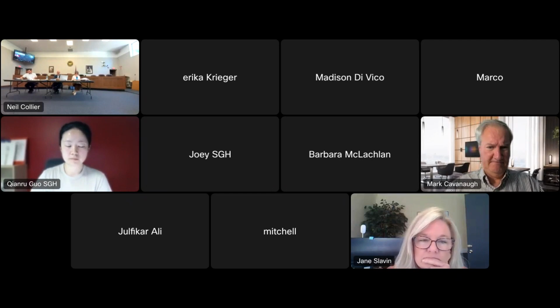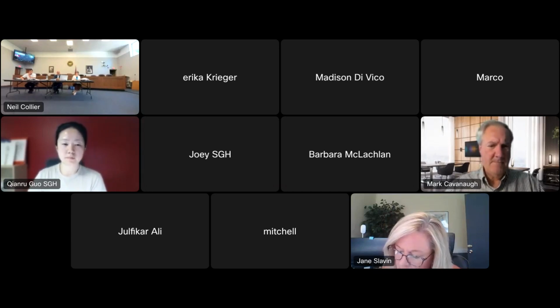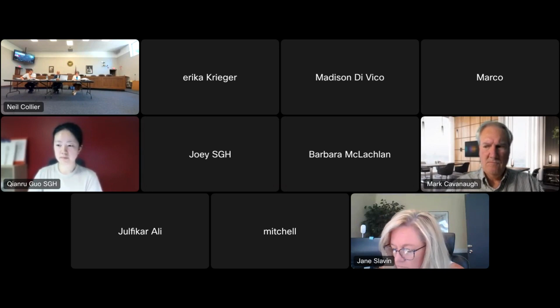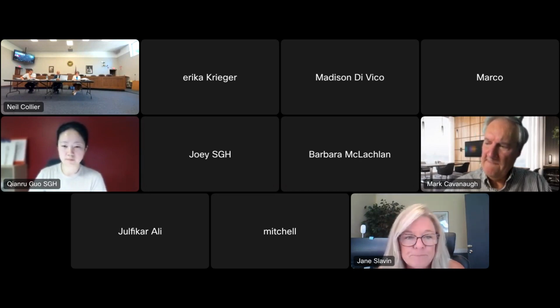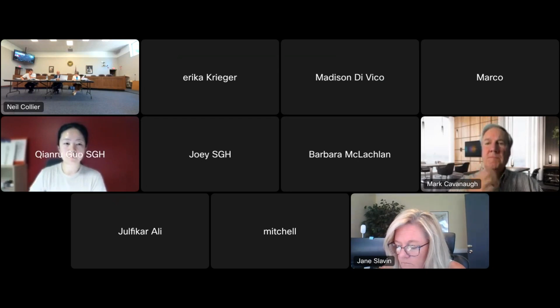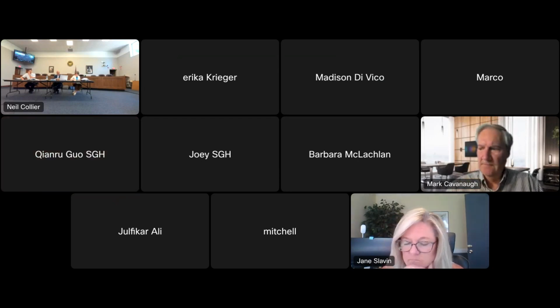Good question. Right now the model reflects a pop-out at the top. These aren't really visible from below or from out on the site, but if you were looking at the shade structure from above, you'd see rectangular panels, give or take 9-foot long rectangles. Four of those are lifted up about 6 inches so rain can't get in, but heat, air, and smoke can pass through. So that gap is modeled into it. They're not hatches that open and close, they're always open, and the size of the openings is what we settled on to get the performance we wanted for not having smoke or fire build up at that plane.